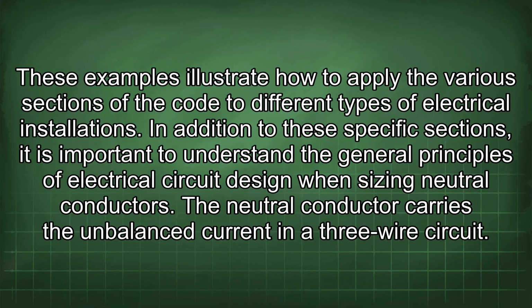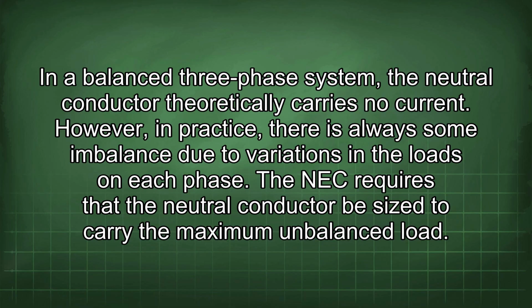In addition to these specific sections, it is important to understand the general principles of electrical circuit design when sizing neutral conductors. The neutral conductor carries the imbalanced current in a three-wire circuit. In a balanced three-phase system, the neutral conductor theoretically carries no current. However, in practice, there is always some imbalance due to variations in the loads on each phase. The NEC requires that the neutral conductor be sized to carry the maximum unbalanced load.